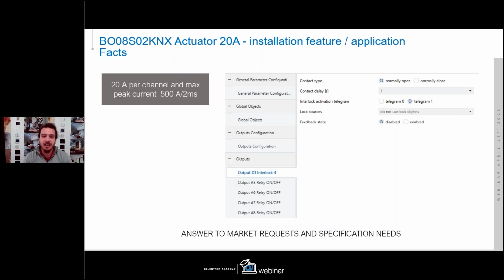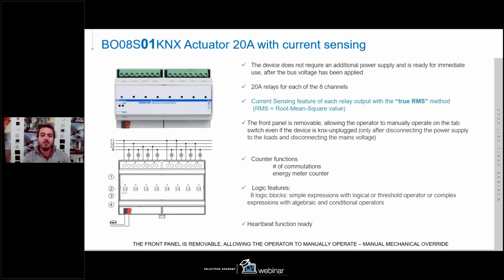ETS, as I said, is the same ETS database that you can find on the F series and the K series of our actuators to control light and interlock. And with the 20 amps relay, we can support up to 500 amps for 2 milliseconds.